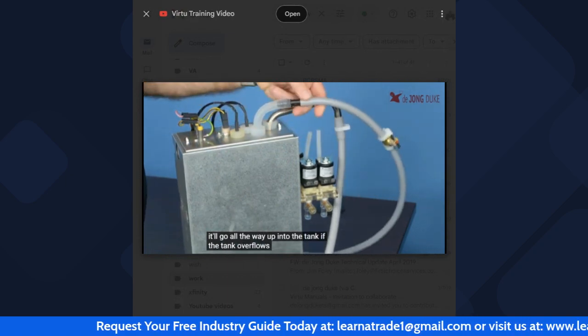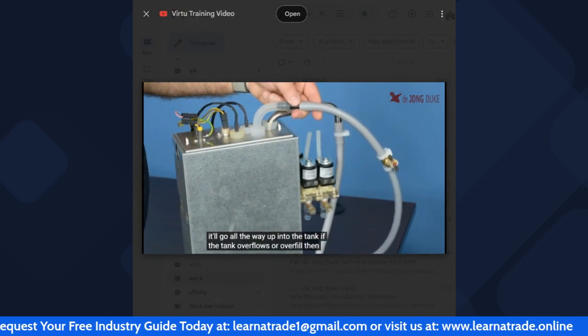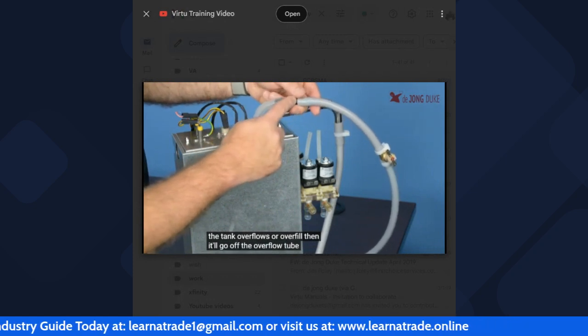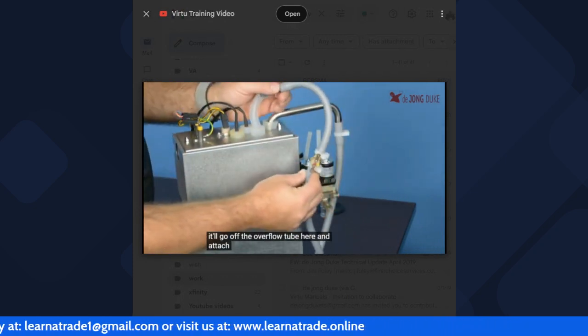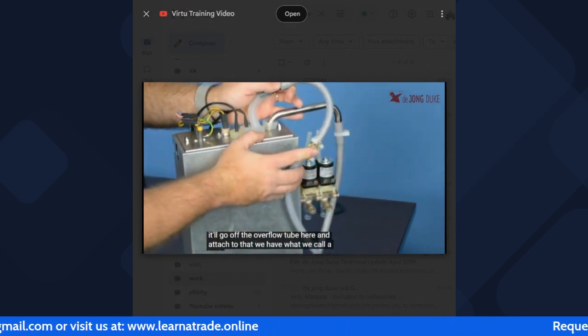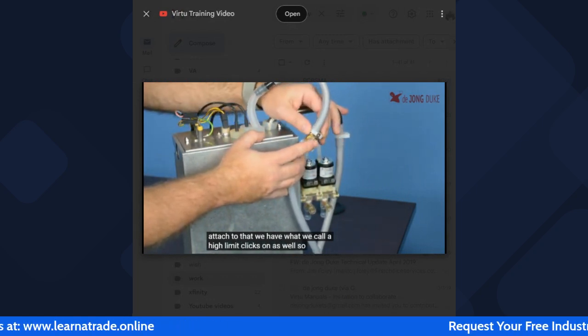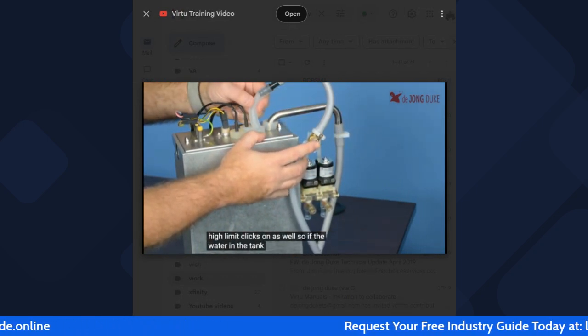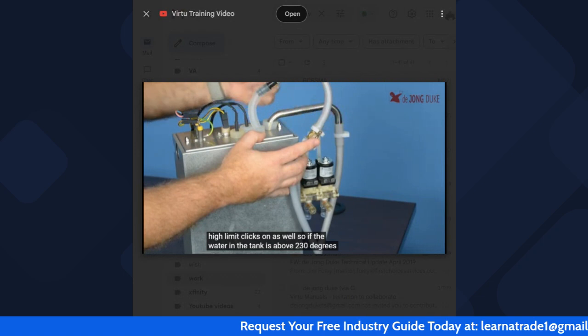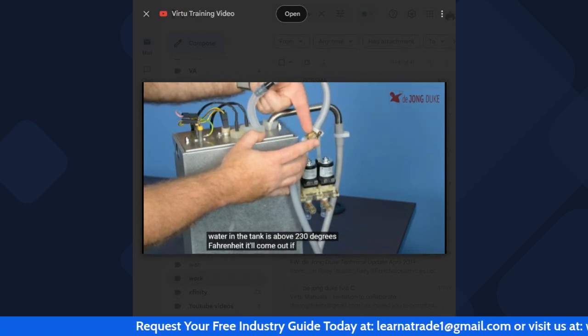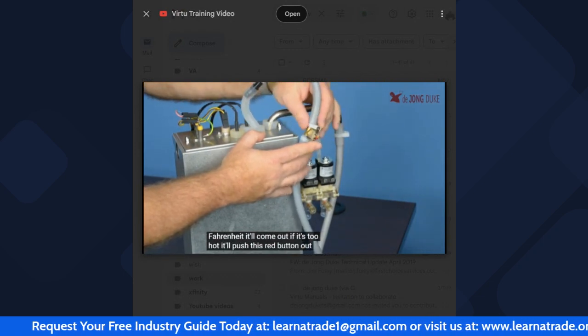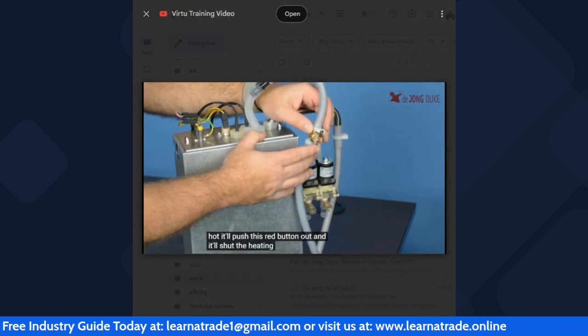If the tank overflows or overfills, then it'll go out the overflow tube here, and attached to that we have what we call a high limit Klixon as well. So if the water in the tank is above 230 degrees Fahrenheit, it'll come out. If it's too hot, it'll push this red button out and it'll shut the heating element off.